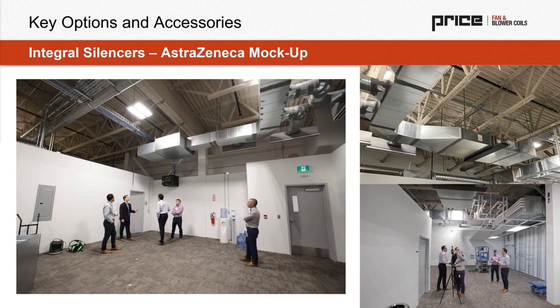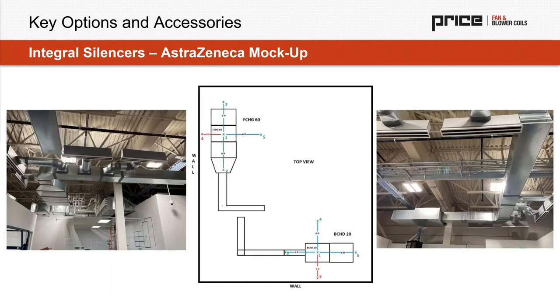So we built this ducted system with a couple different pieces of equipment in our facilities in Winnipeg. In this case, it was an open ceiling install, very representative and close to what would be envisioned on the AstraZeneca project. However, not as pretty and a little bit more rugged. It's a testing mock-up space, a little bit louder than what would be seen in AstraZeneca as far as background noise, being located close to a factory. And additionally, a little bit different from a space constraint perspective. We installed multiple products: slot diffusers, the Price SDS model, plenums, duct silencers as specified and laid out in the mechanical plans, but two large pieces of fan and blower coil equipment, our Genesis high performance FCHG fan coil and our direct drive draw through blower coil, the BCHD.